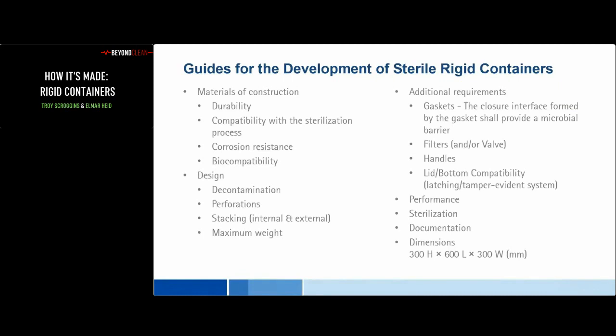One of the key areas that's different too is, like I said, we tend to go into more detail than the global standards, but one area they go into more detail, and Elmar alluded to this, is really the dimensions of the sterilization unit. Can you talk about maybe why that's important, Elmar? Yeah, that's one more detail which is really specified in the ISO standard and in the EN standard for containers, and it's about sizes. As you know, standards are made to make sure that things just fit together. Just to make sure that screws and nuts, for example, fit each other and are not developed in totally different ways and directions. And so the ISO standard includes that a container, including all connected parts such as carrying devices, shall fit within one sterilization module.